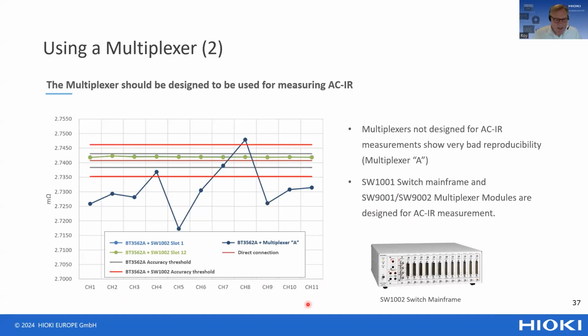The same test was performed with the multiplexer card in slot 1 of the mainframe instead of slot 12. I can't show you this graph because it's completely underneath the green one. This shows that it makes no difference which slot of the mainframe the multiplexer card is in, which is important because you want to be able to compare measurement results.